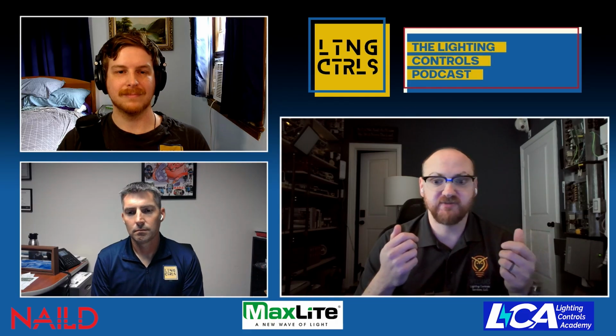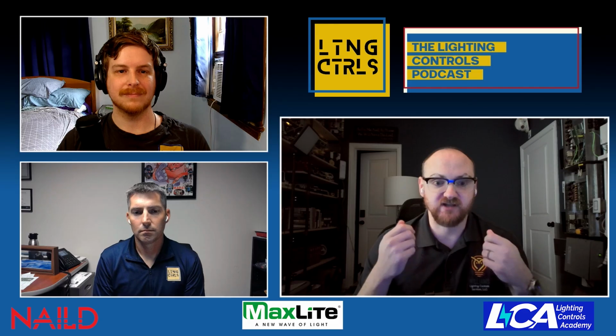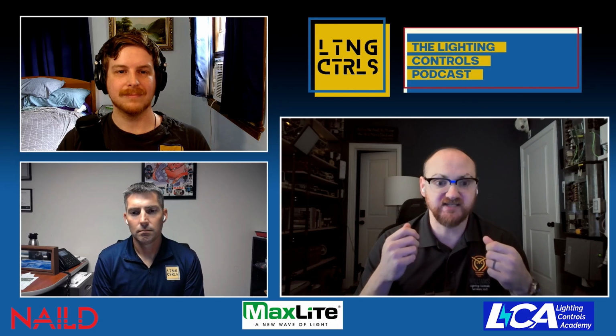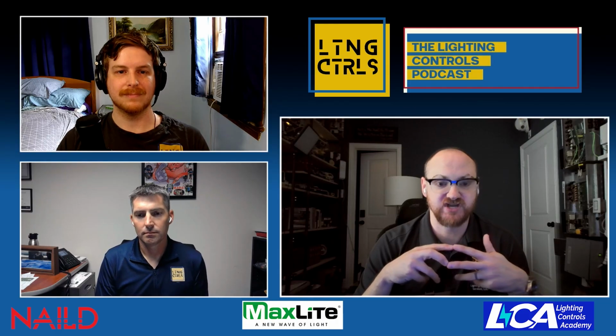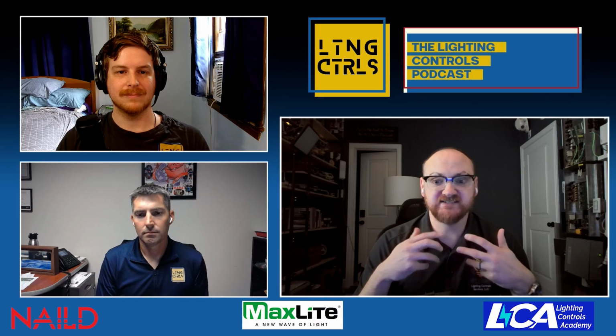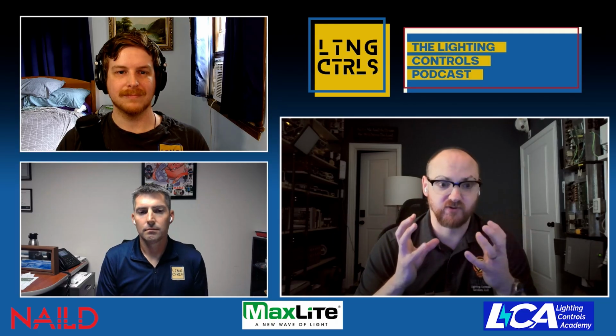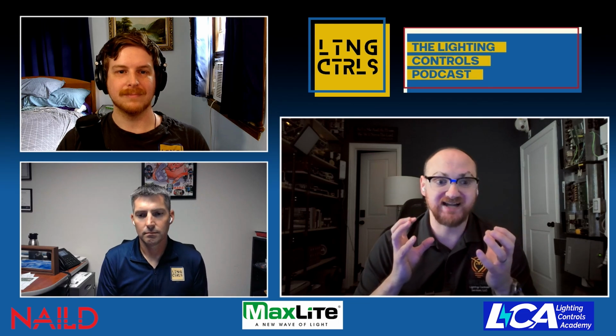There's ways of doing this without having to actually see the lights turn off. It's a matter of being still long enough to watch the LEDs on a sensor, looking for false triggering from airflow or heat. So it's watching the LEDs around you, knowing that if I can stand still for 20, 30 seconds and see if this sensor can roughly time out, then chances are I'm not getting airflow issues. And if I know the air is on, then I'm not going to get a false trigger at this time.